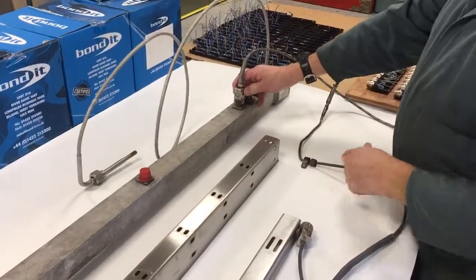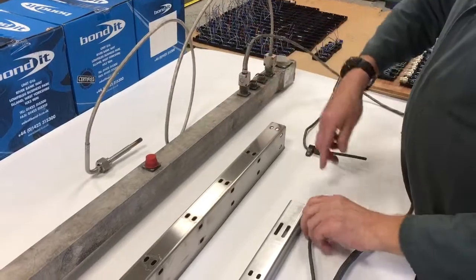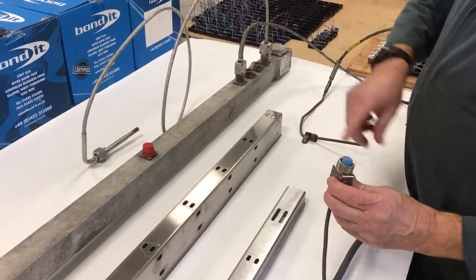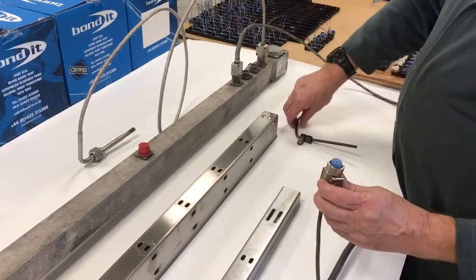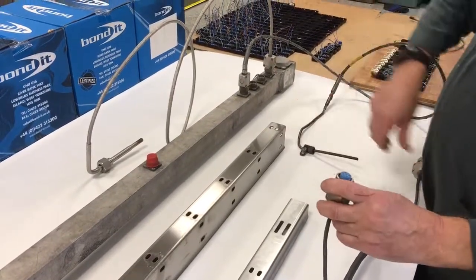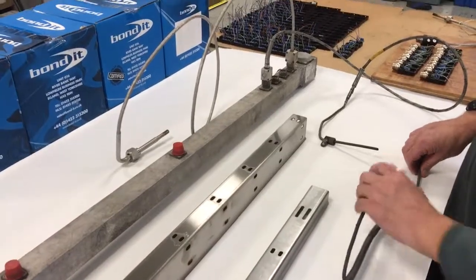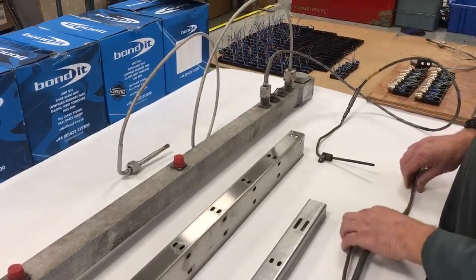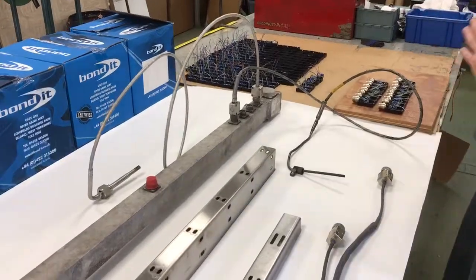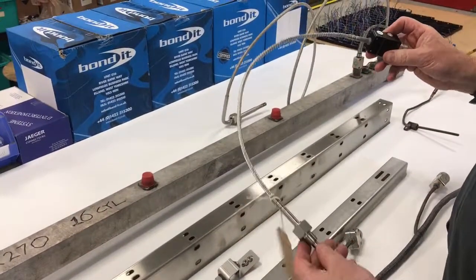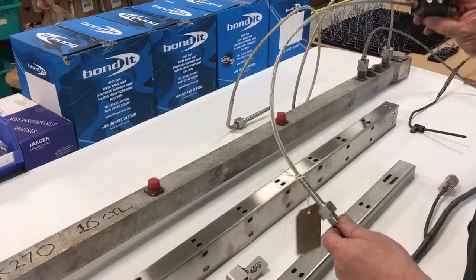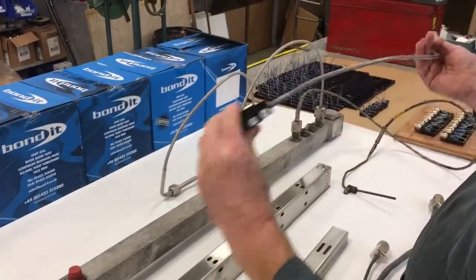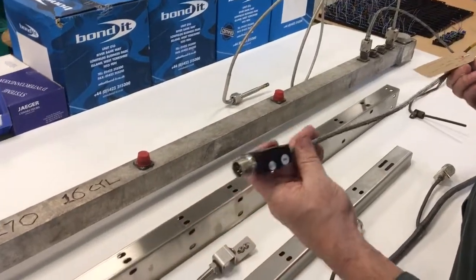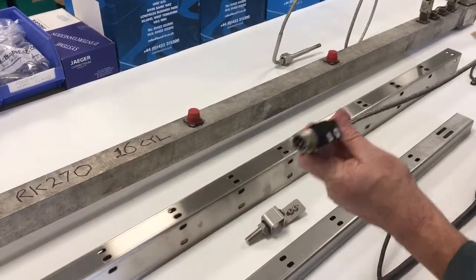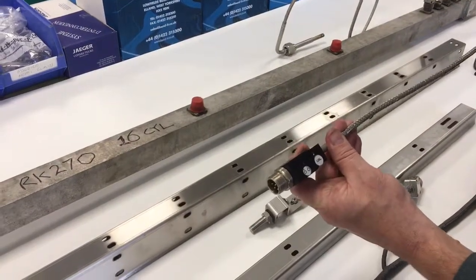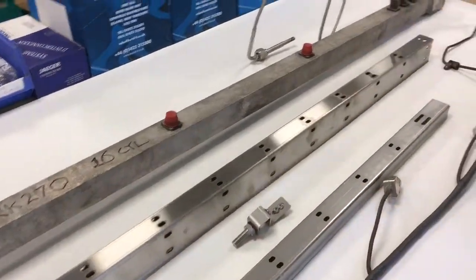Both are interchangeable, and we can make this type of sensor with the male connector, or we can take stock and put your male connectors onto it. If you had large quantities of stock, we can convert them so that they will be suitable with our transmitters. To show you now with the transmitter, this is another engine manufacturer's sensor, and this is fitted with a signal conditioner, 4 to 20 milliamps, and this particular one has the facility to do onboard calibration, which I will demonstrate now.